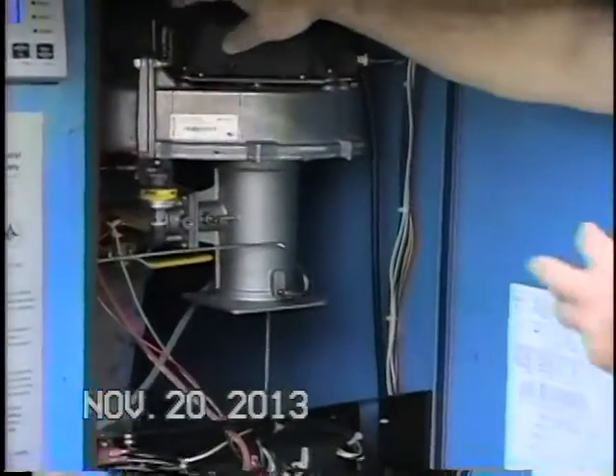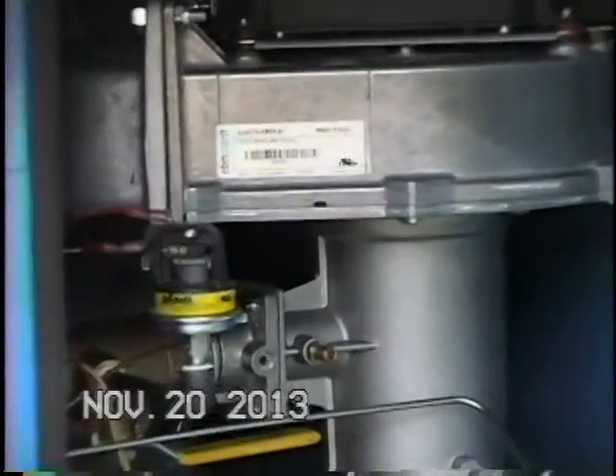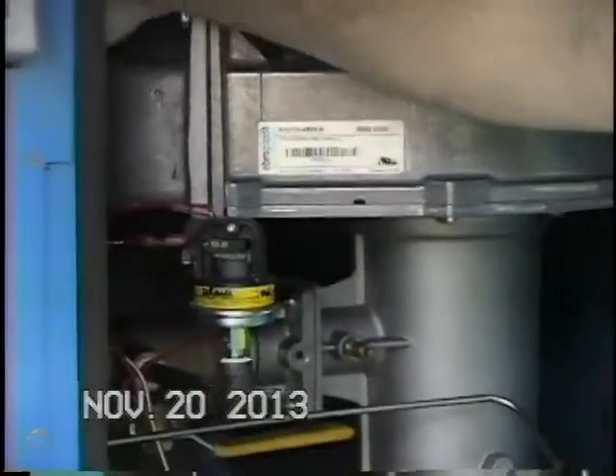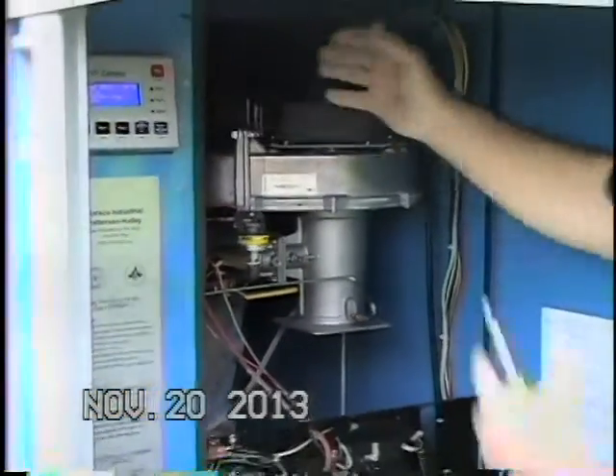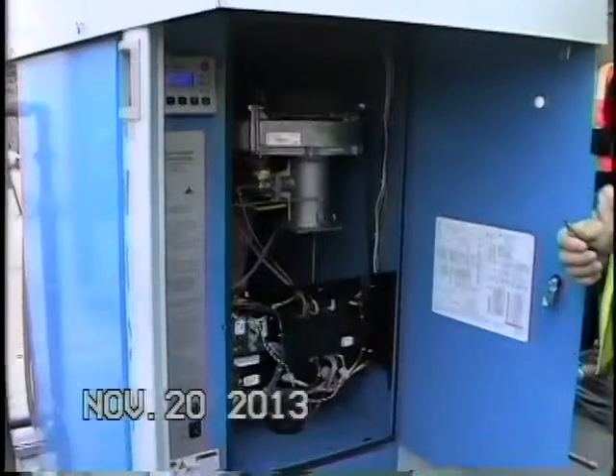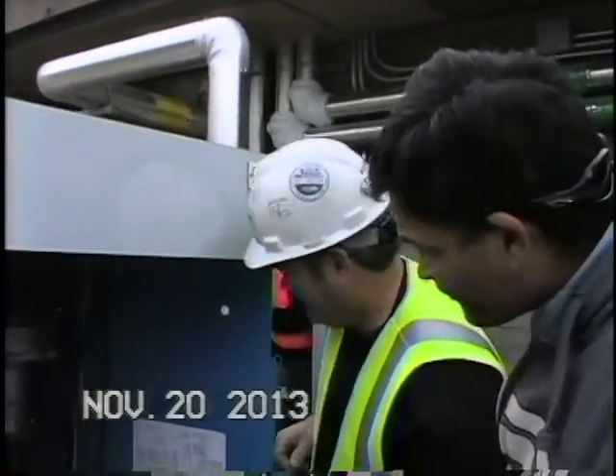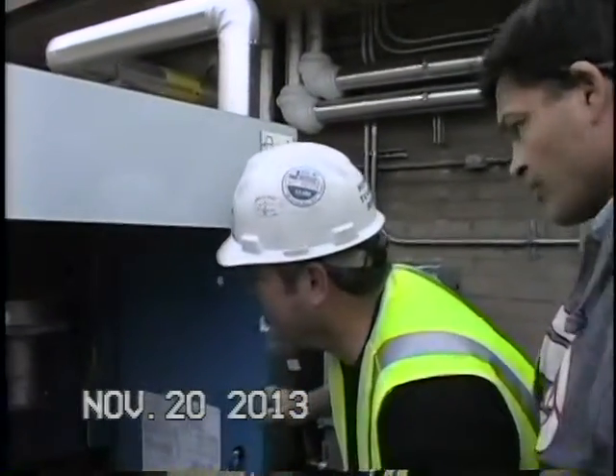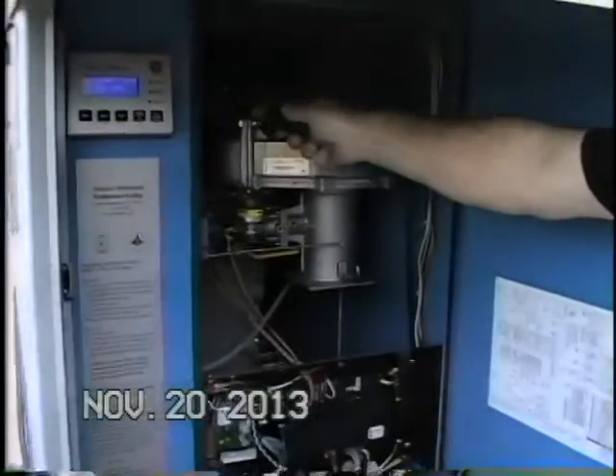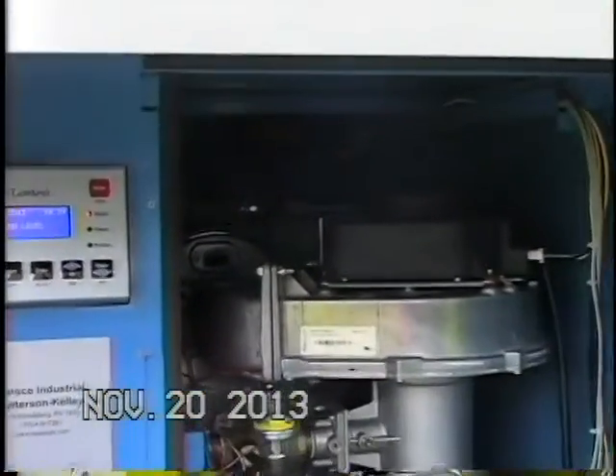Now, when we talk about the middle part to pull out, you have to pull all this out to get to the burner assembly, which is inside there. So all this has to be disconnected and come out. And then it's right there behind, right where this is your igniter. So all that has to come out. So again, it's not that difficult, but I highly suggest you guys get trained on that before you try that. Okay. And then here's your, see that back in there? That's your manual high limit. Okay? So all those controls in your gas, high and low, are inside the back there.